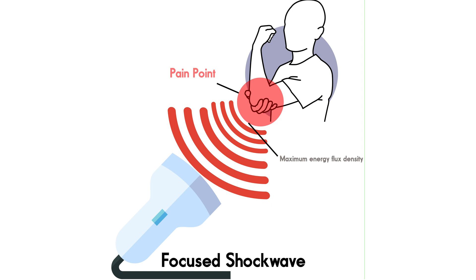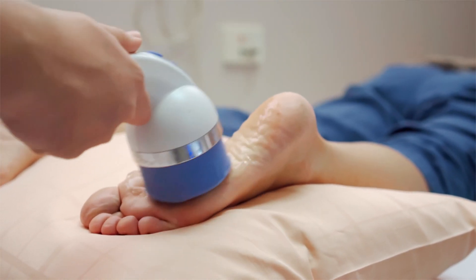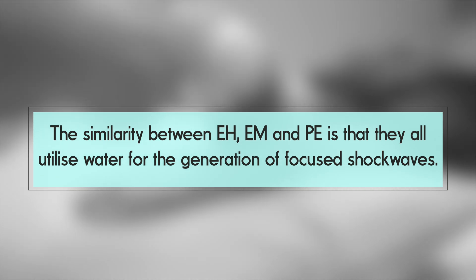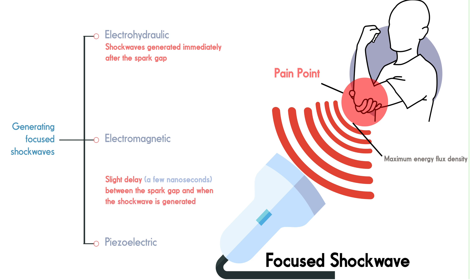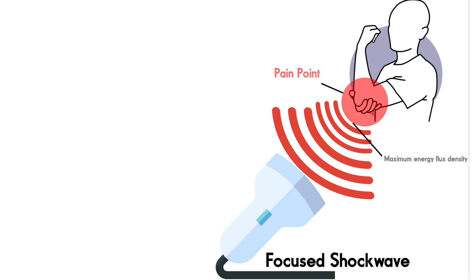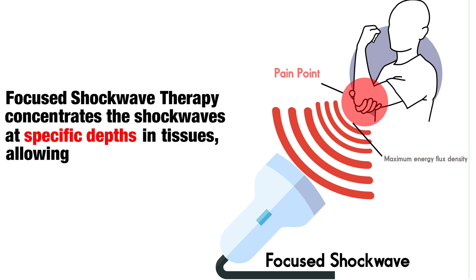Now there are two main kinds of extracorporeal shockwave therapy: focused shockwave therapy and radial shockwave therapy. Focused shockwaves can be created in three ways: electrohydraulic, electromagnetic and piezoelectric. We don't need to delve too much into the technicalities of these methods. The thing that is common to each of these three is that they all use water to generate focused shockwaves. They differ with respect to the moment at which the shockwaves are formed. Focused shockwave therapy concentrates the shockwaves at specific depths in tissues, allowing targeted treatment.